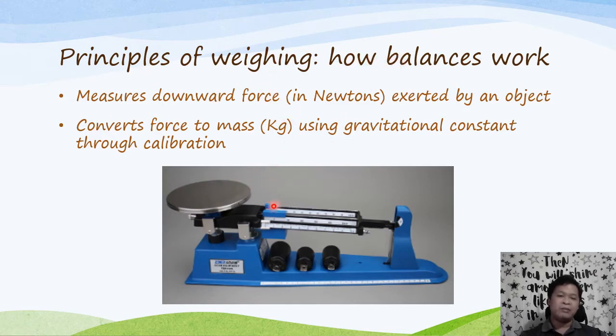So how do balances work? Again, when you have a balance, you ideally have the weighing pan and the counter weight or yung weight na pang compare. So how this one works is you move these slider weights. No? Parang yung timbangan lang madalas nakita nyo sa ospital na may parang height measurement din. So it's just a smaller version of that. And then as you can see, yung parang pinaka fulcrum niya ng seesaw is over here. Okay. So you slide the weight bars and kapag balance na doon sa equivalent weight dito, yung pinatong mo, ay yung arrow nito nandun sa middle, di ba? Parang may diamond dyan, and sa middle yan tuturo. Okay. Then of course you can use these calibration weights, or rather extra weight, sorry. Yan, isasabit nyo dito sa dulo. Mas mabigat yung kailangan ninyo.